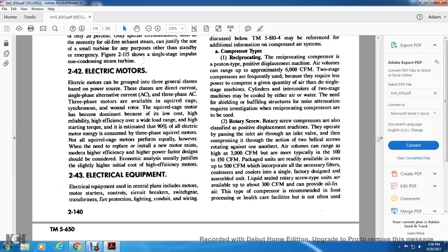However, when motors need to be replaced or new motors installed, modern higher-efficiency, higher-power-factor designs should be considered and economically analyzed. Usually the savings justify the slightly higher initial cost of high-efficiency motors.